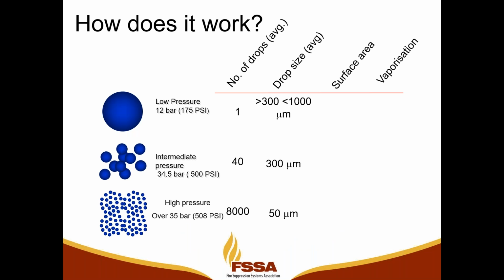So when looking at low pressure, intermediate pressure, and high pressure water mist systems, if you're taking a drop of water, a low pressure system is typically going to break those droplets into sizes of greater than 300 microns, but less than 1,000 microns. When you're dealing with intermediate pressure, it's going to break the water into 300 micron droplets. And then with high pressure, they're typically breaking it into 50 micron droplets.